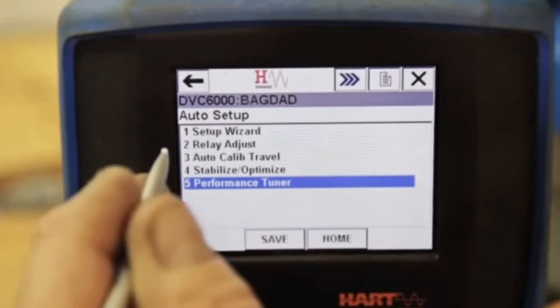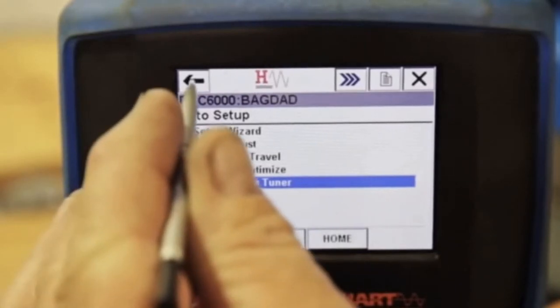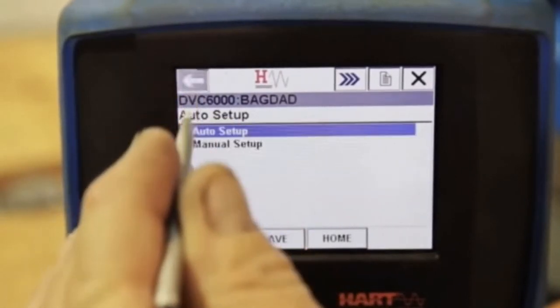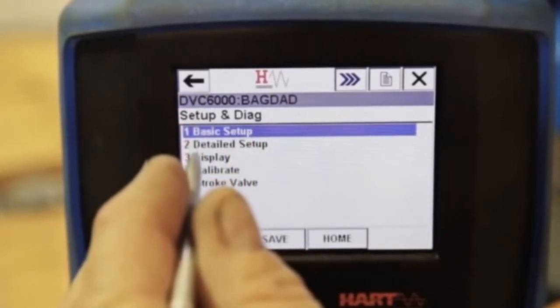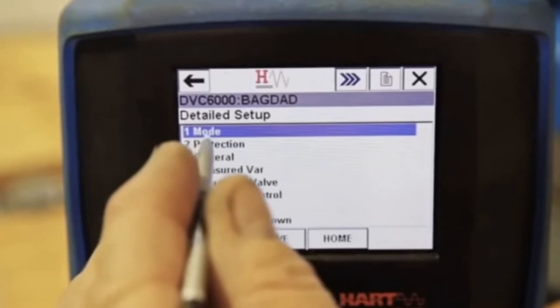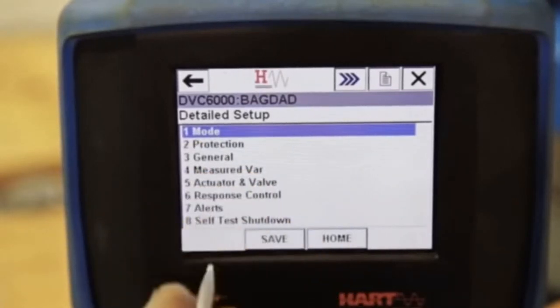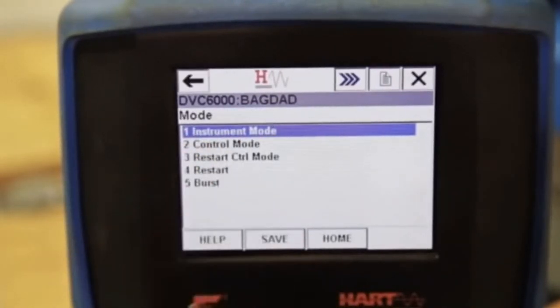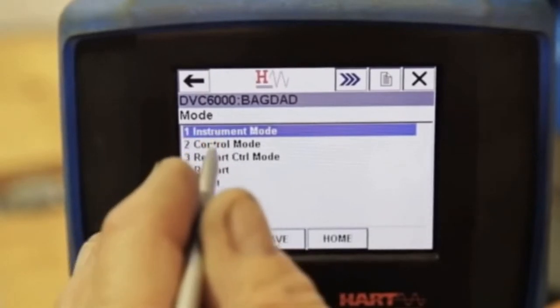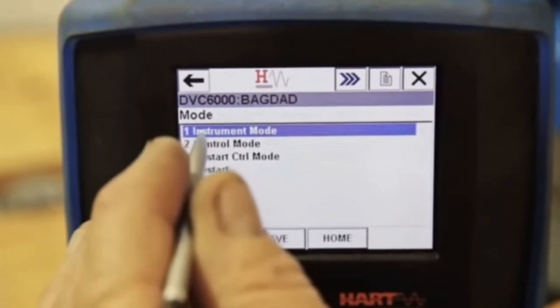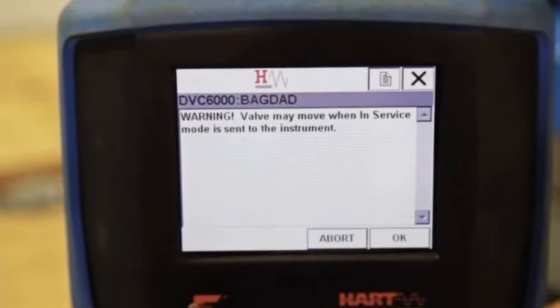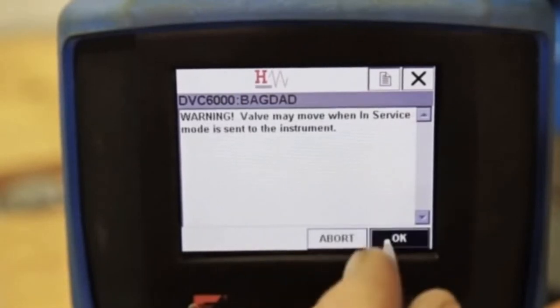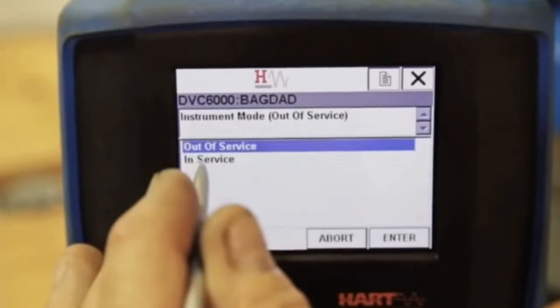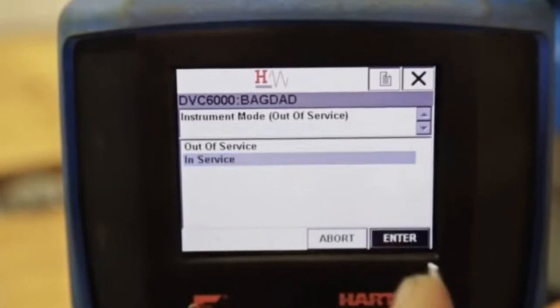Arrow back to the Setup and Diagnostics screen to put the instrument back in service. Select Detailed Setup, Mode, Instrument Mode. A warning that the valve may move when in service mode will appear. Put the instrument back in service.